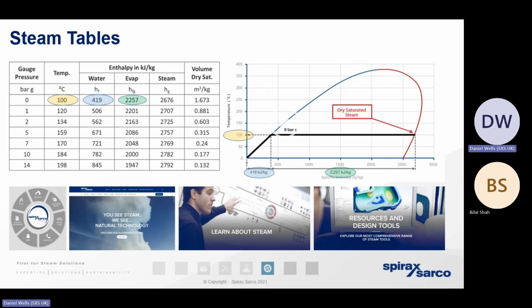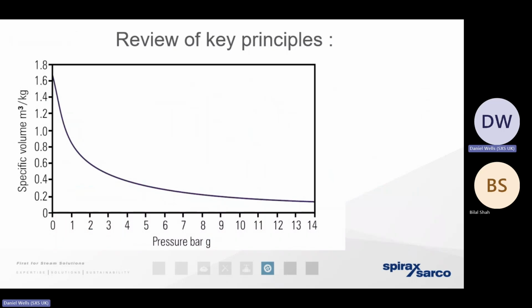So it's critically important that we do everything we can to ensure the steam condition or the steam quality stays on or as close to that red line as we possibly can. Not just for maintenance issues, not just for process time issues, but also for those inefficiencies. The cost of steam is critically important. And it's something that you'll keep hearing me rattling on about in future presentations. So pulling together those relationships, kilogram of water, 0.001 cubic meters, boils off to give us steam as a gas at 0 bar gauge, and it expands by 1600 times.